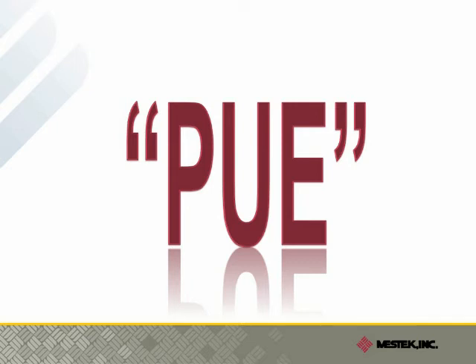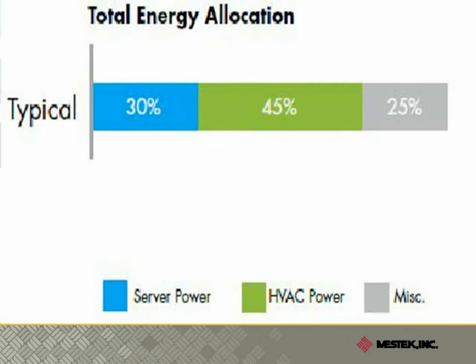PUE is actually an acronym — P-U-E — standing for Power Utilization Effectiveness. It is a measure of the total electrical demand of the data center building divided by the electrical demand of the IT equipment itself — a measure of how efficiently the data center operates at full load. The average around the U.S. is about 2.5, meaning the building uses 2.5 times the energy of the IT equipment installed in it, implying quite a bit of waste. The servers themselves are only a small part of the total energy used, with conventional HVAC cooling making up the bulk of the building energy demand.